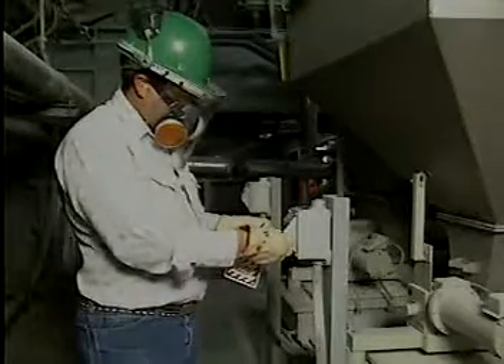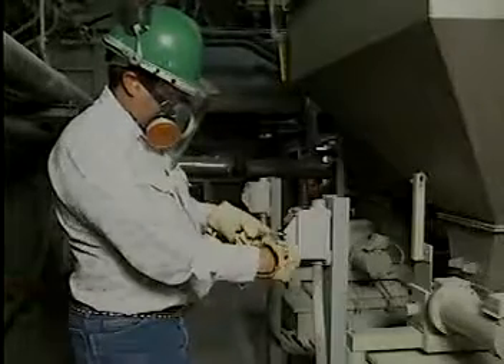This allows equipment to be locked out of service so that it can be worked on safely. Another procedure, known as racking out a breaker, can be used to physically lock out a load from its source of power so that de-energized equipment can be worked on safely. Racking out a breaker involves physically disconnecting the breaker from its electrical connections.